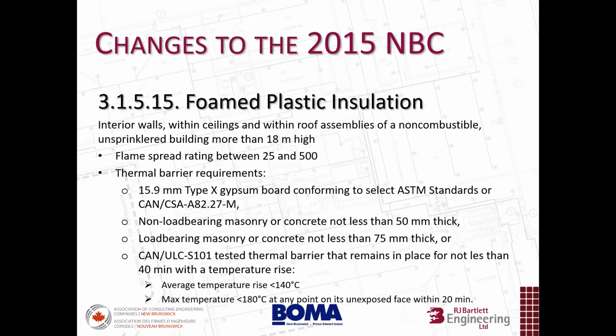And so if you do have it in your interior walls, within ceilings, within roof assemblies of non-combustible construction on a unsprinklered building that is more than 18 meters high, you can see how, and we have a flame spread rating of between 25 and 500. We now get into a Type X 5/8 gypsum board thermal barrier, non-load bearing masonry or concrete no less than 2 inches thick, load bearing masonry concrete no less than 3 inches thick, and then some increases there in the CAN-ULC S101 test as well.